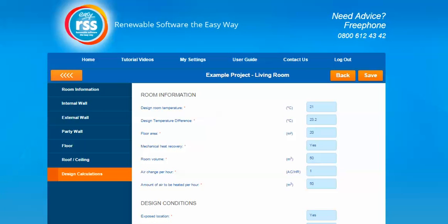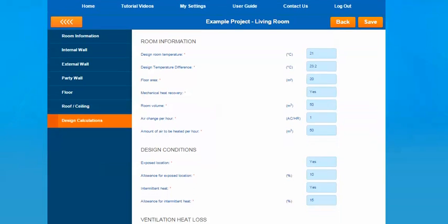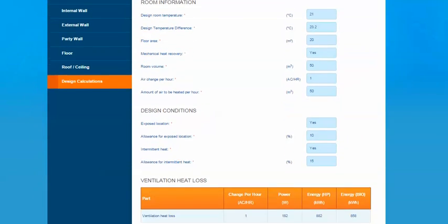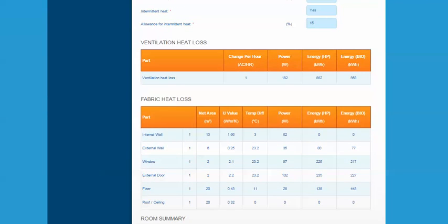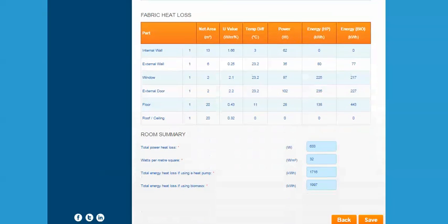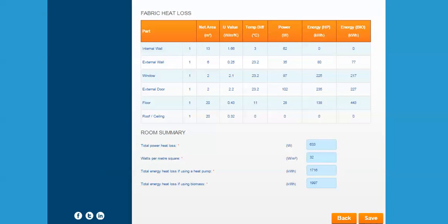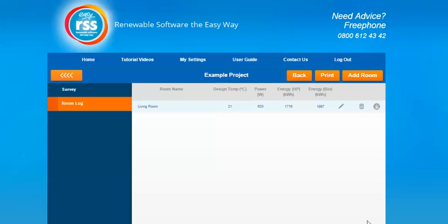Once you select next, the design calculations based on the information just input about that room will appear. You'll see the basic room information you put in to start with, details about the design conditions, and then a table showing the ventilation heat loss and the fabric heat loss. At the very bottom you have a total power heat loss, watts per metre squared, and total energy heat loss for the heat pump and biomass. If you click save it will then take you back to the room log section and that room will appear in your list. You then have an option to edit that room by clicking the pencil icon, delete the room, or download a document output for that room.